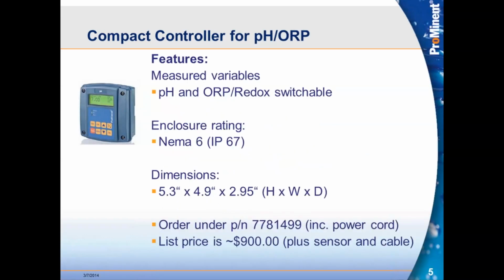The measured variables, again, just to repeat, are pH and ORP redox, referred to as ORP. And it's switchable. In the field, you can program it to be either. So if you want to stock one on the shelf to have very quick delivery to a customer, the only thing that you don't want to stock would be the sensor. Either one of those sensors, we're not recommending that you stock. Leave that to us. Here in the winter months still, we insist that we ship those overnight.